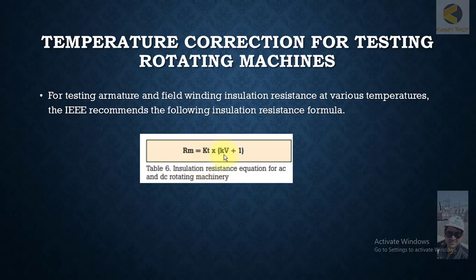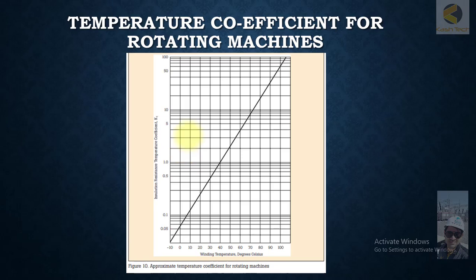The formula is RM equals KT times KV plus one. Table 6: insulation resistance equation for AC and DC rotating machinery. This is just an example I have shown you from IEEE. They are recommending this formula.